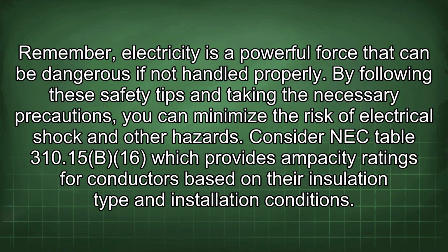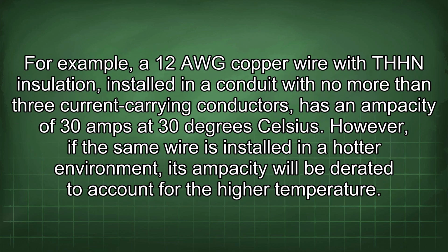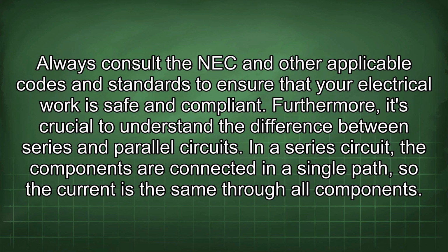Consider NEC Table 310.15(B)(16), which provides ampacity ratings for conductors based on their insulation type and installation conditions. For example, a 12 AWG copper wire with THHN insulation installed in a conduit with no more than 3 current-carrying conductors has an ampacity of 30 amps at 30 degrees Celsius. However, if the same wire is installed in a hotter environment, its ampacity will be derated to account for the higher temperature. Always consult the NEC and other applicable codes and standards to ensure that your electrical work is safe and compliant.